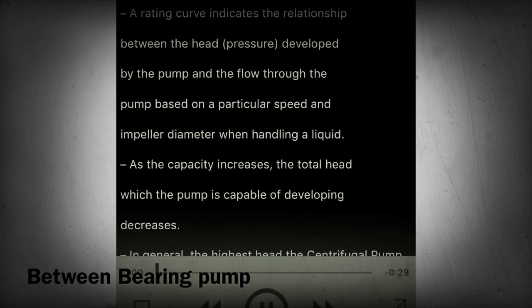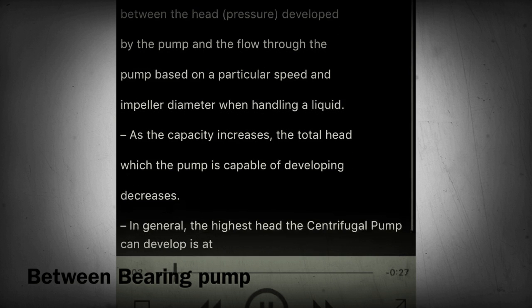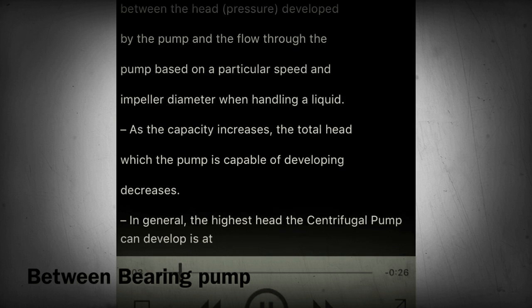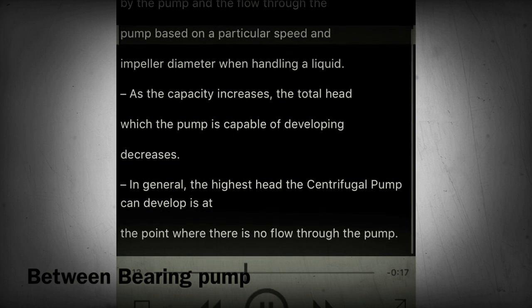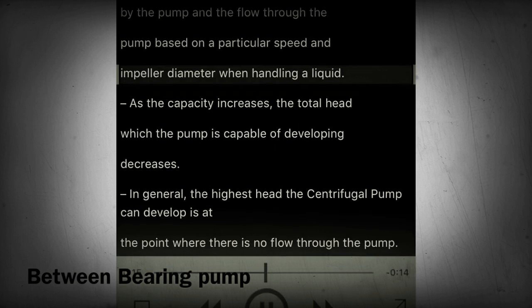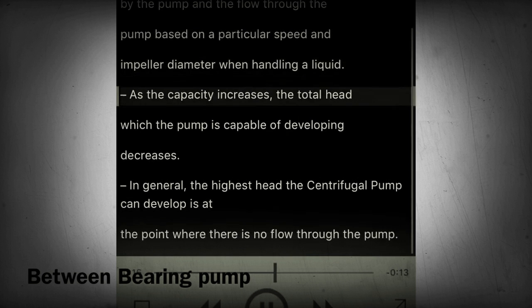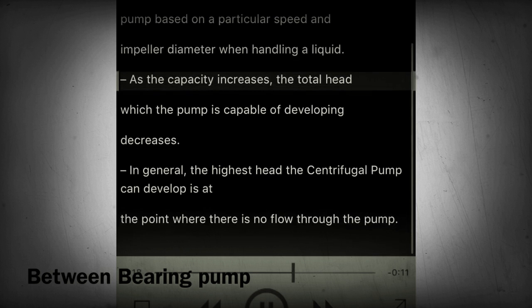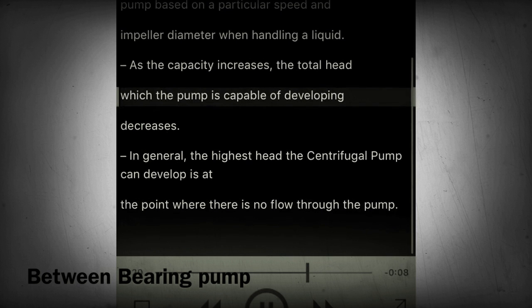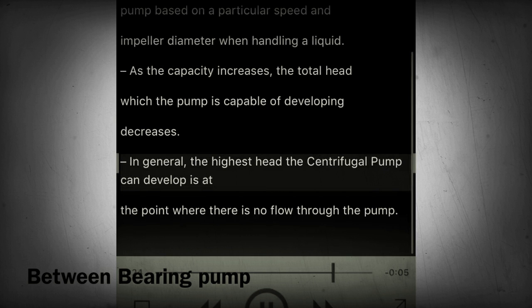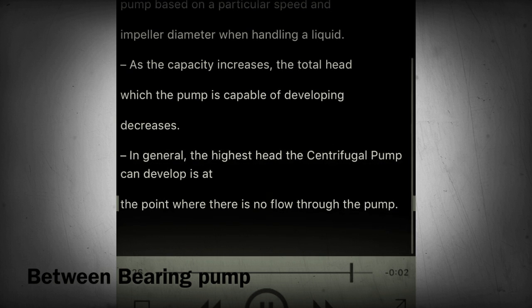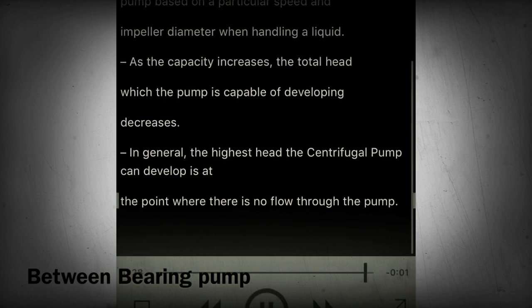Section 22 - Centrifugal pump curve characteristics: head and capacity. A rating curve indicates the relationship between the head (pressure) developed by the pump and the flow through the pump, based on a particular speed and impeller diameter when handling a liquid. As the capacity increases, the total head which the pump is capable of developing decreases. In general, the highest head a centrifugal pump can develop is at the point where there is no flow through the pump.